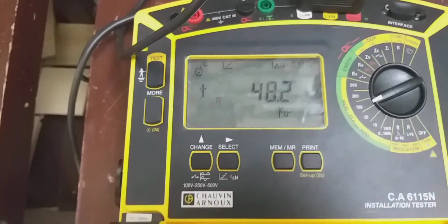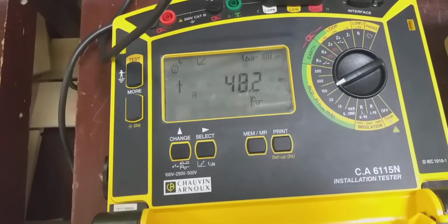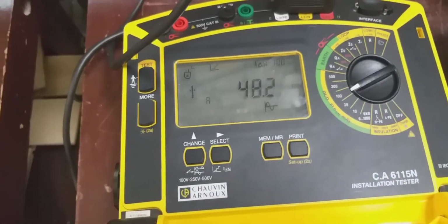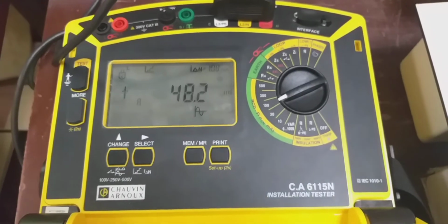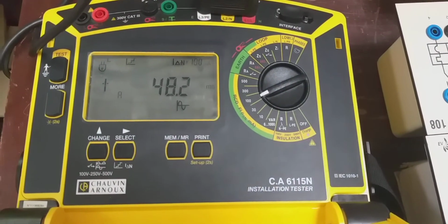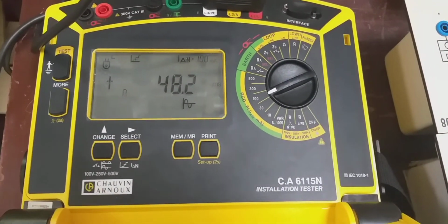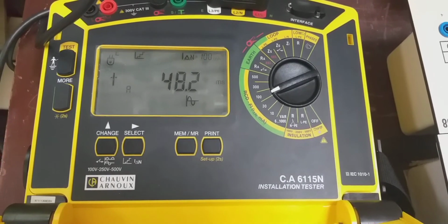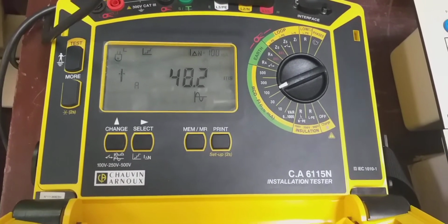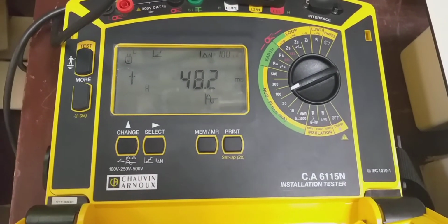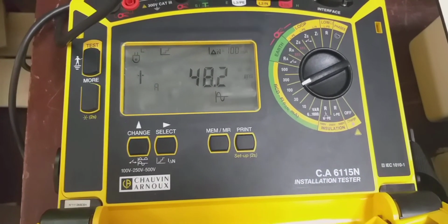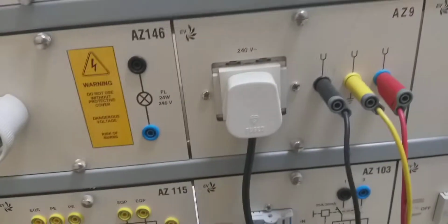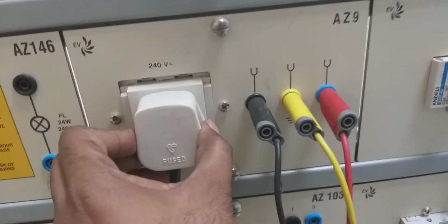So this is how we conduct the activity for activity number 3. So from this activity we come to know how to measure the loop impedance, and then touch voltage and the prospective short circuit current, and also whether the RCD is in good working condition or not by checking the trip current and then tripping time. Okay, so the same procedure can be done by using this card with the extension card.